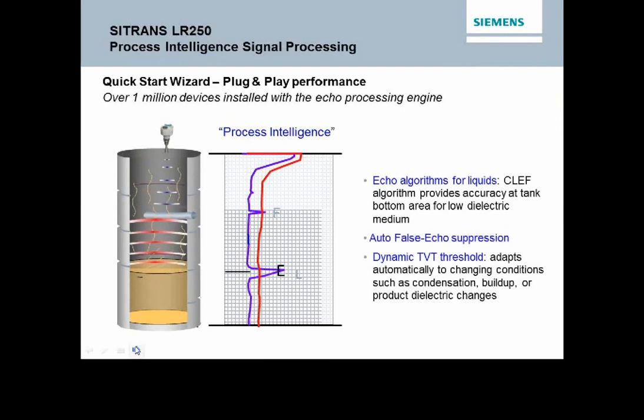We can also adjust the algorithms for liquids. We can adjust for low liquid levels where the radar might pick up the bottom of the tank. We can also do something that we'll call auto false-echo suppression, and this is dynamic. One of the keys with this is that we actually use the strength of the echo signal, and we'll go through that in a moment, to automatically change and adapt to conditions. So we're not static. We can adjust how we're measuring based on the feedback that we're actually getting.